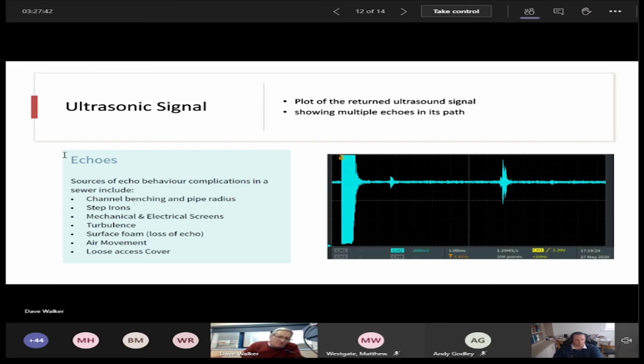Here, what we're showing on the right is the ringing, which is that big, large area at the beginning of that plot, and then you've got multiple echoes. Now you'd like to think that this larger echo down here is your true signal, but it isn't. The large echo is here at the start. And you've now got to develop algorithms to say, is it this small echo here? Is it this echo here? Or is it this very little one down here?